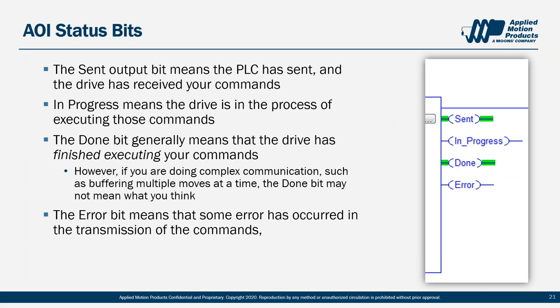'Error' is more nuanced — it can indicate either an error in sending a command to the drive or an error in command execution itself. The most common cause I've seen is a sequencing error where two AOIs attempt to send commands at the same time, putting both in an error state. The exact condition of Done and Error depends on the specific AOI — for example, if you send a relative move and the motor stalls, you get the Error bit set. If you plan to use Done and Error meaningfully in your code, dig around in the AOI code and check AppNote 46 for your specific AOI.